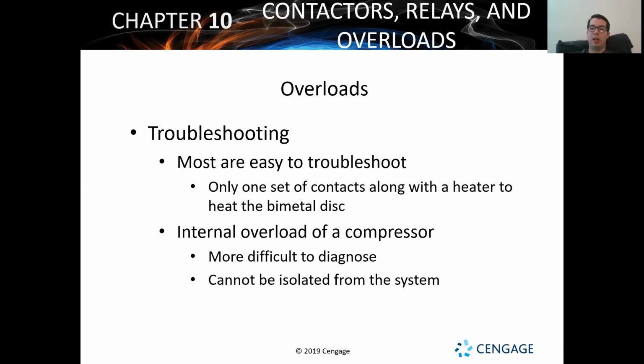And so if you have power, and let's say you've got power at the breaker panel, and you've got power at your disconnect, and you've got power at your contactor, you got power coming out of your contactor, and then on the other side of your contactor, you've got an overload device. You got power getting to your overload device, but then you check and you see power's not going from your overload device to your motor. That's where it stopped.